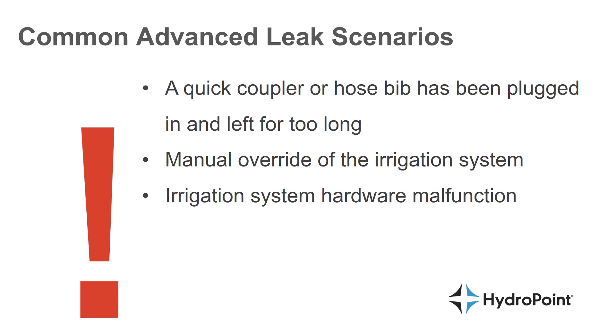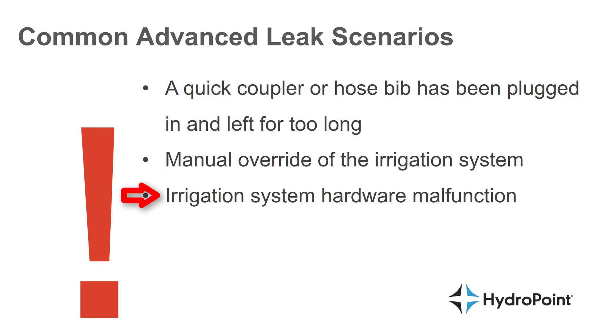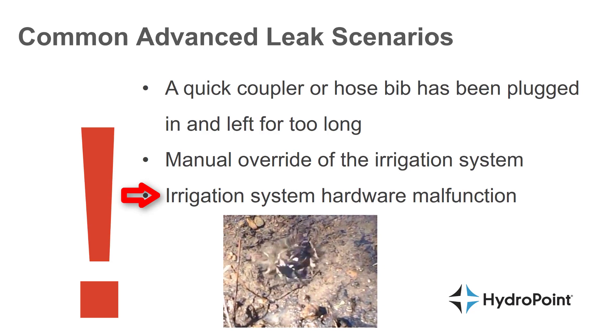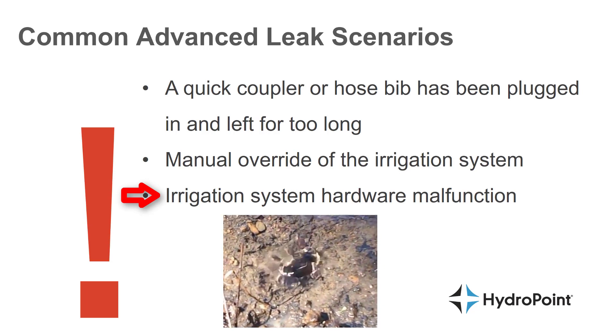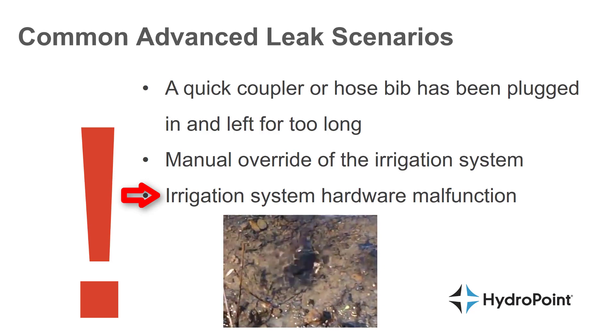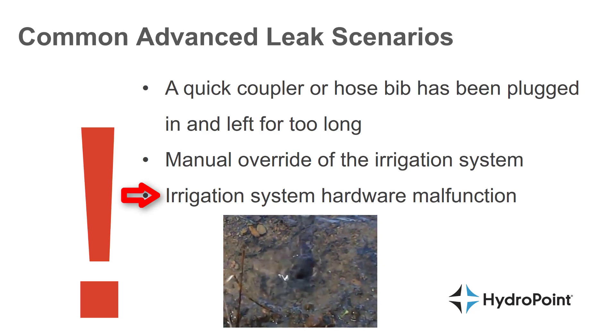While these kinds of conditions can be caused by hose bibs and quick couplers, they can also be caused by a manual override of the irrigation system — sprinkler techs opening valve boxes and manually overriding valves by opening the solenoid or the bleed screw. In a more high-stakes scenario, an advanced leak can also mean a malfunction of your irrigation system. For instance, if a mainline fitting comes loose and starts to leak water, this would be another example of an advanced leak scenario.